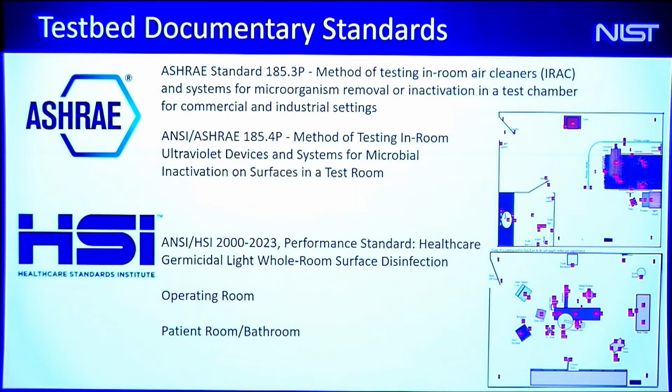In the US, there's a number of documentary standards going on from IES and ASHRAE, and I would call these more what I call test bed type of measurements, validation that the system works in a controlled environment. And when you look at these, there are no radiometric requirements for the measurement of the device. They're all biological indicators. And that's just because radiometry is somewhat of a bad name.